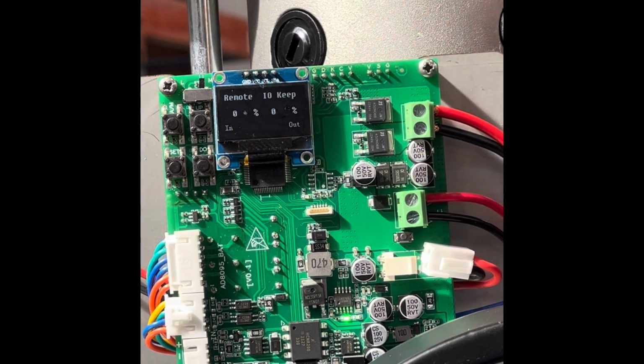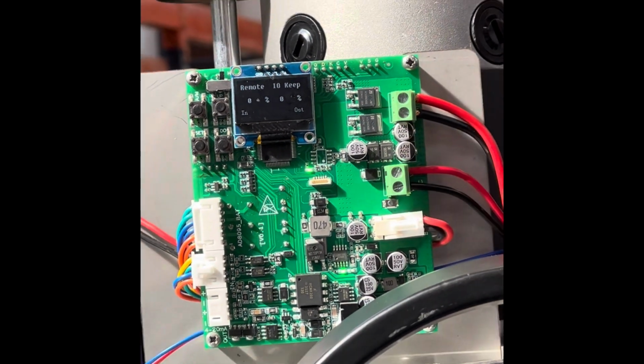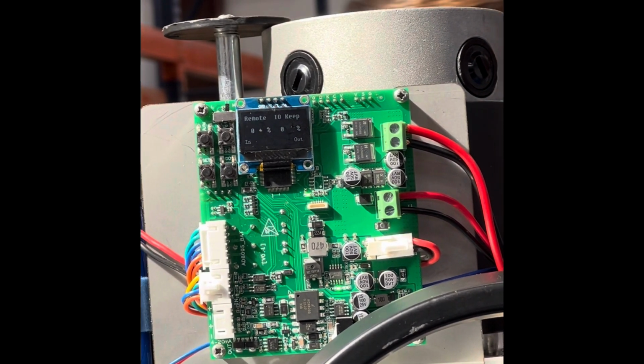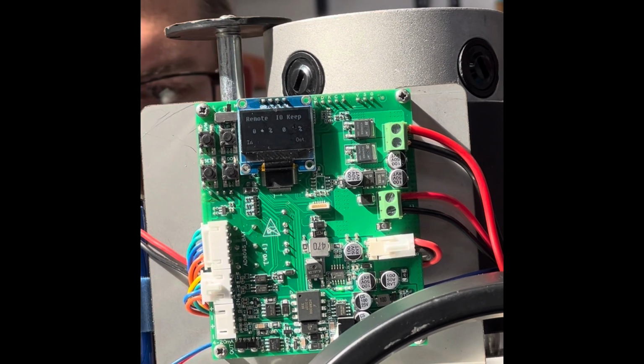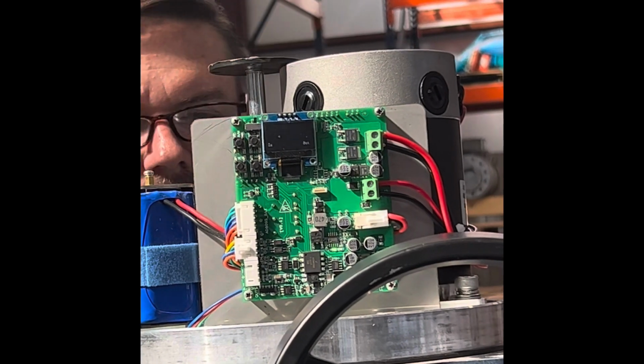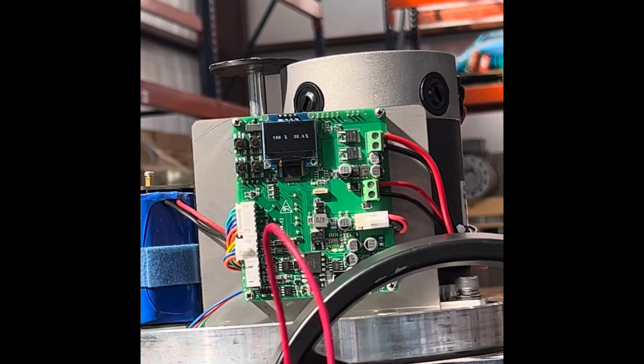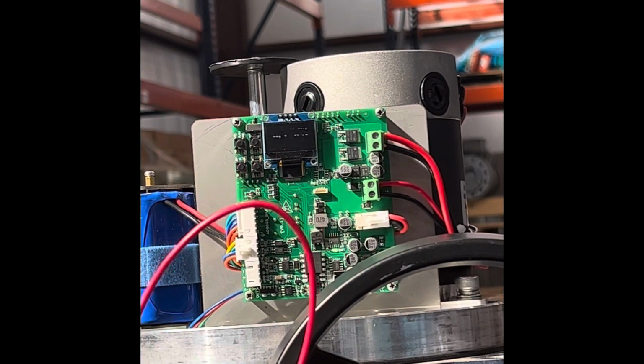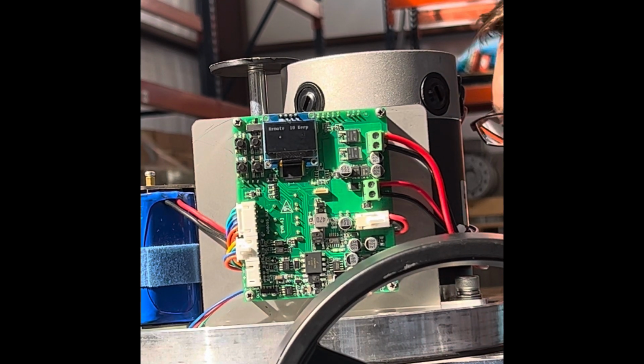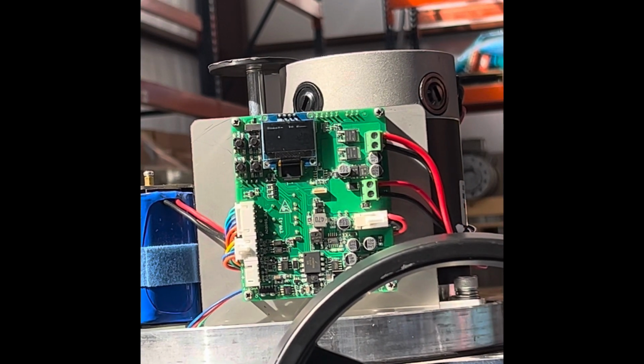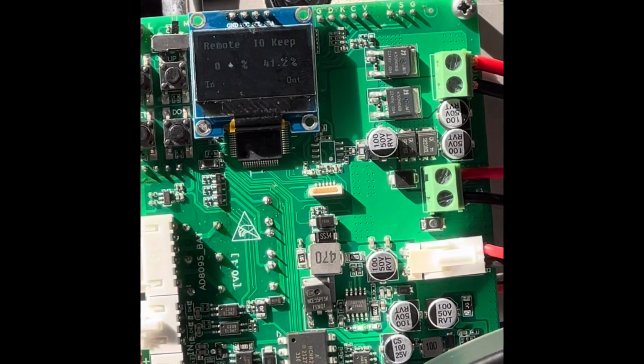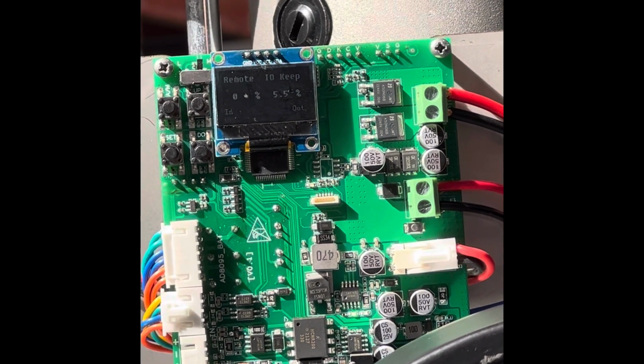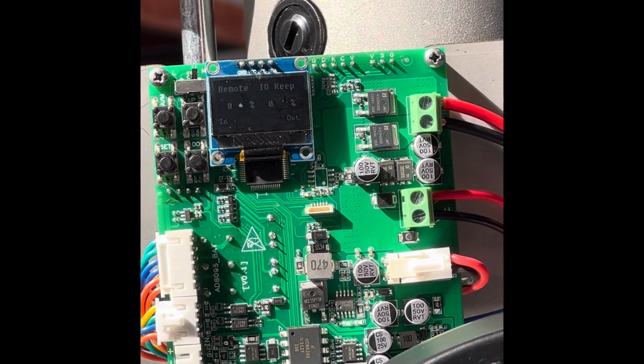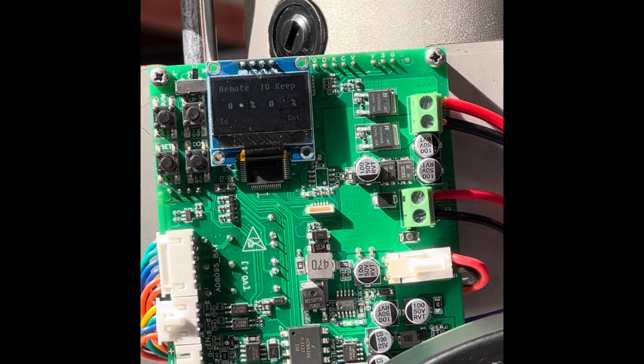Okay, so we're gonna run this real quick. So I'll come back over here and cycle it. Just for the demonstration, I gave it the signal by providing contact between 3 and 4 to go counterclockwise. Now to go clockwise, I'll use the same wire to go 3 to 6. This being a fast cycle actuator, this runs in 10 to 12 seconds, and it has battery backup, and torque output is 5,310 inch-pounds.